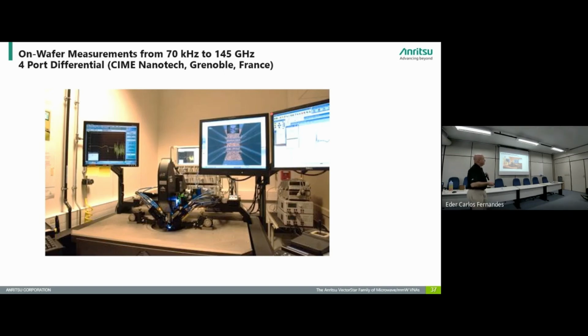I mean, at 40 gigahertz, there may be some arguments for automating, because it just speeds things up. But you've got to be concerned about the substrate surfaces too. They're not perfectly flat. So again, there's this concern that when the probe backs off and moves to the next standard, it somehow hits the probe the wrong way, and you just can't afford to have that kind of accident. So I think the manual way to go is best. But yeah, for lower frequencies, I've heard of some automated cases as well.